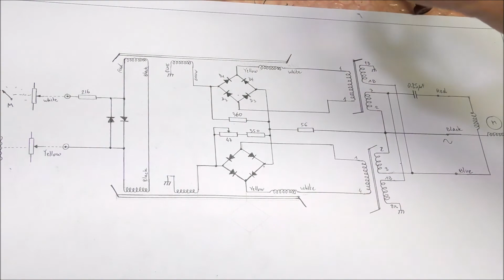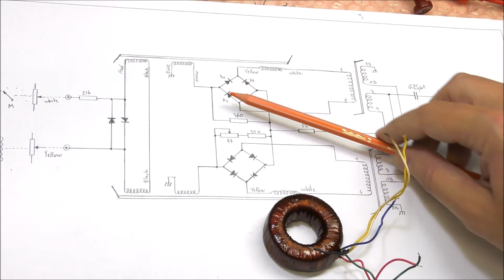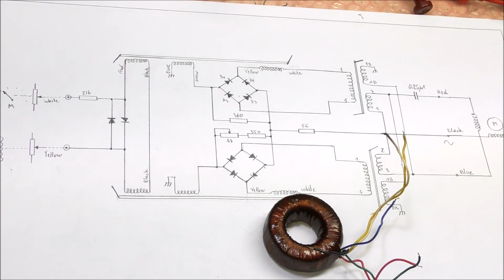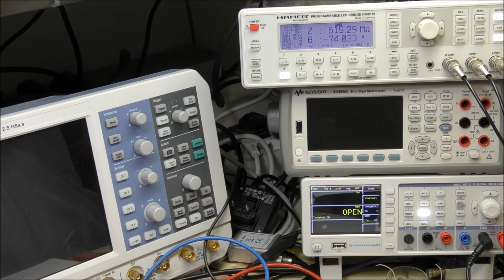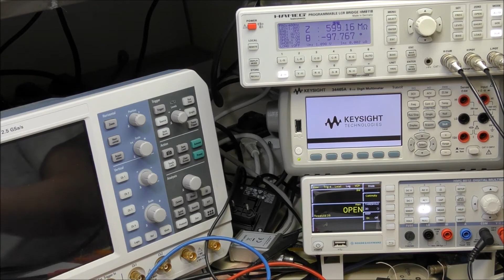Maybe we can make some tests, for example, with this transformer, which is this one here. So we can measure the impedance in this winding here, while applying a DC current in that winding. So I will change the orientation of the camera to see the impedance on my LCR meter here, like that. I will measure the current with this multimeter, and the impedance will be measured with the LCR meter here. I will try to zoom out in order to see also the transformer. Okay, so I will measure the impedance between the blue and the green.